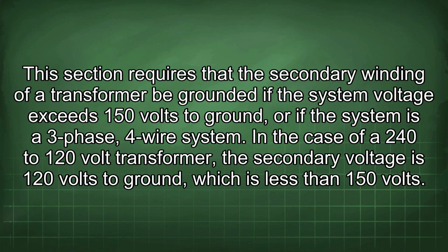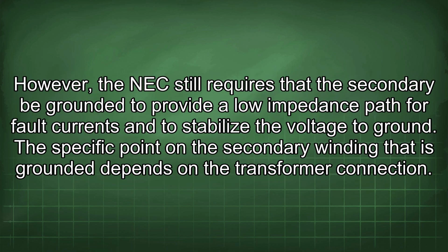This section requires that the secondary winding of a transformer be grounded if the system voltage exceeds 150 volts to ground, or if the system is a three-phase, four-wire system. In the case of a 240 to 120 volt transformer, the secondary voltage is 120 volts to ground, which is less than 150 volts. However, the NEC still requires that the secondary be grounded to provide a low impedance path for fault currents and to stabilize the voltage to ground.